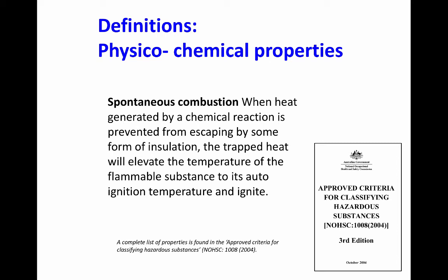When linseed oil oxidizes in air, or dries, it generates heat. The oxidized components act as an insulator to prevent the escape of heat generated by further oxidation. This leads to spontaneous combustion. Spontaneous combustion needs no external energy source. Now, all of these definitions have the approved criteria for classifying hazardous substances. So this is the NOHSC 3rd edition, which is from October 2004.